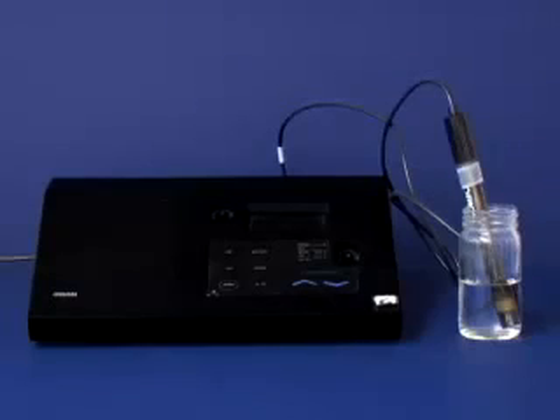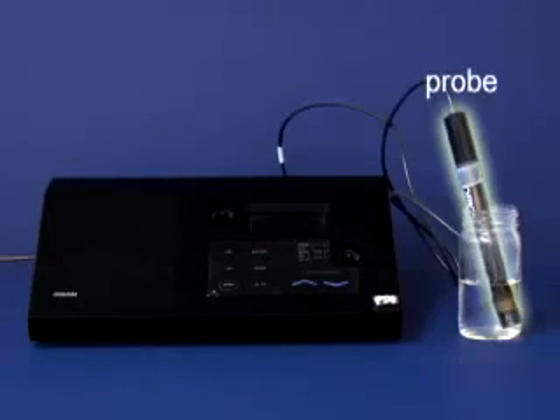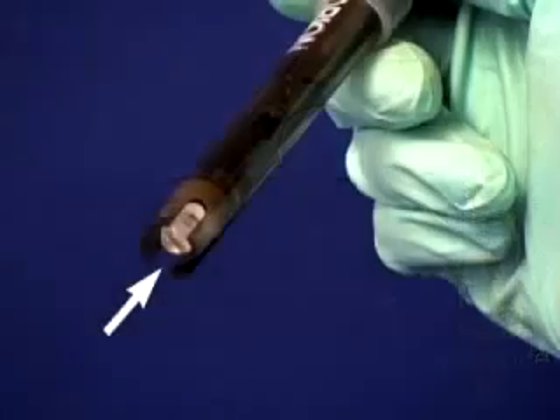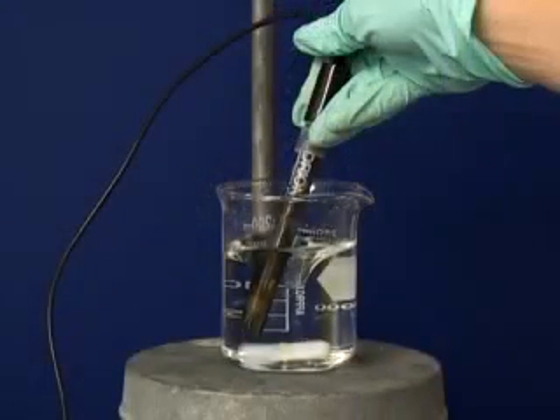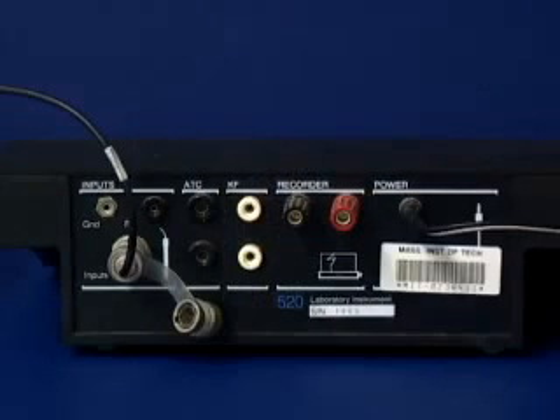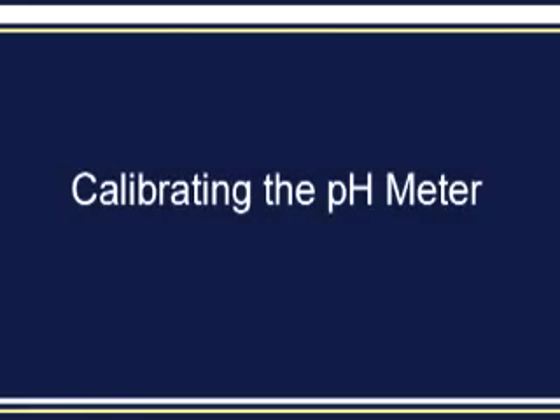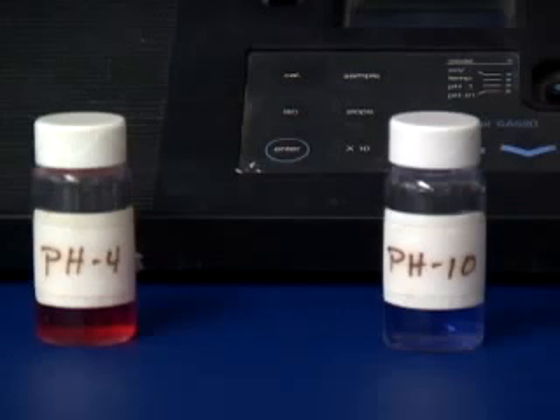The important components of a pH meter include the display, the probe, and the electrode tip. The electrode tip contains a fragile glass bulb. Be extremely careful not to hit the probe on the side of a beaker and when using stir bars. To operate the pH meter, first make sure that the electrode is connected to the meter. Then calibrate the pH meter. The pH meter must be recalibrated every time you turn it on and after 3 to 4 hours of use. We will perform a 2-point calibration. This method involves calibrating the pH meter with 2 different buffers of known pH.